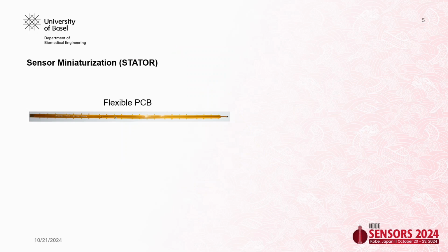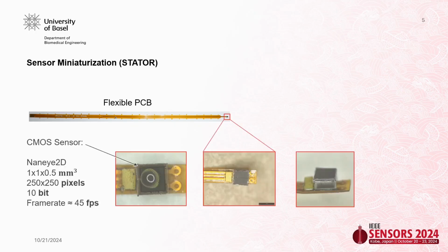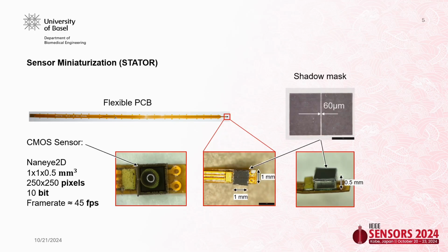The idea is to use a flexible PCB that would also be our cable to transfer all the data from the camera. On the tip of the system, we install a 2D camera that is a CMOS sensor with a size of 1 by 1 by 0.5 millimeter. On top of that, we put the shadow mask that has a 60 micron slit in the middle. We glue it on the top. We have the LED placed below the image sensor, and we have the light blocker shown before.